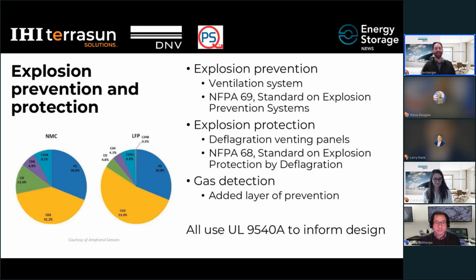Some of the shortcomings: the gas composition test data we get relates only to a single battery cell. So when we're trying to determine toxic hazard risks from a more engulfed, entire BESS unit fire, this doesn't really inform those hazards. It doesn't give us a full analysis of the gases. There are many plastics, electronics, and paints within a full BESS enclosure that would burn in an engulfed fire scenario that aren't considered in the UL9540A gas composition tests.